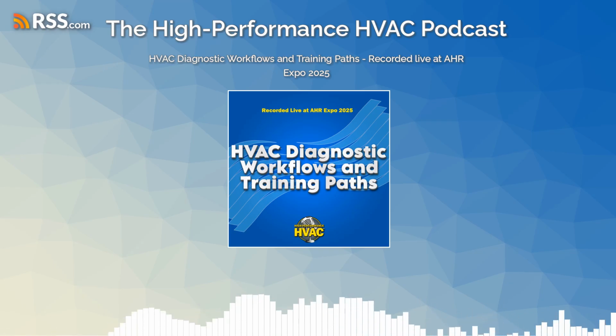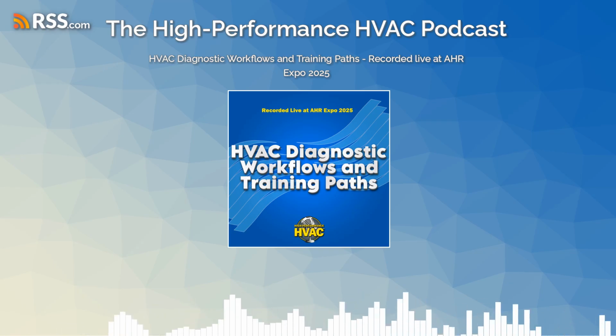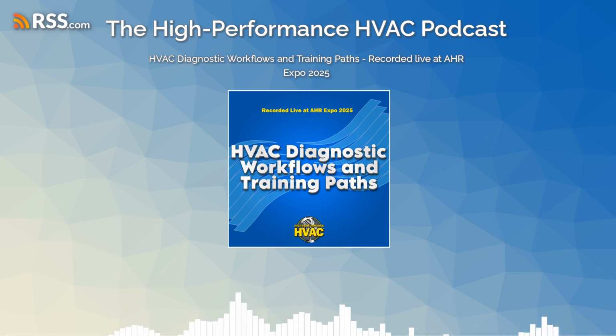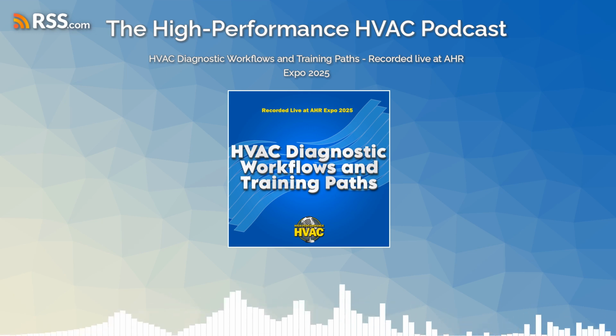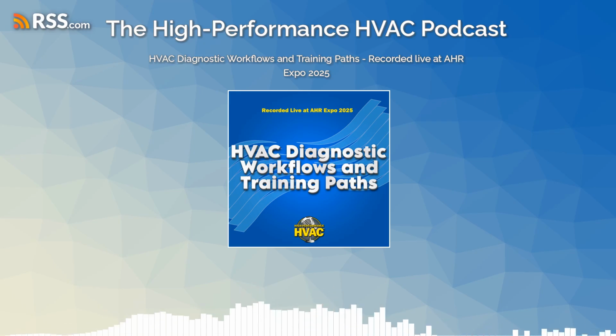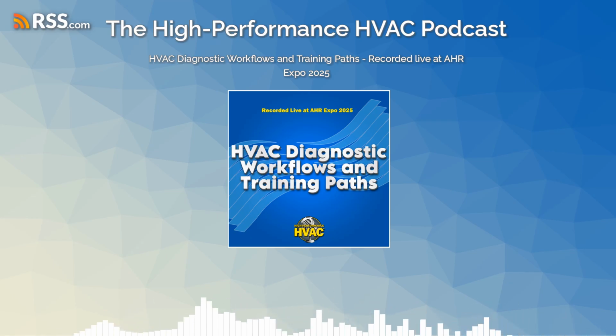Mm-hmm. And the thing is, we always talk about at NCI, if you're going to use the generic fan tables, if you have the OEM available, use the OEM. But this is something for when you cannot find it, if this is an old piece of equipment, or you can't get a model number. It's gone. You know the nameplate tonnage, and you got to make somewhat of an educated decision here. This will get you close. It's a let's-get-close.